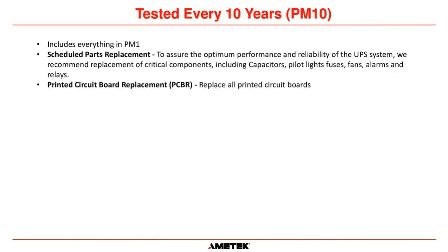And then the last maintenance schedule we have is every 10 years. Okay, a PM10. So that includes everything in the PM1. It also includes replacing the critical components, and that includes the capacitors, the pilot lights, fans, alarms and relays, and all of the circuit boards within the UPS. So it's pretty much you're ripping out the inside of the UPS and you're replacing all of the age-degrading components to make sure you still have a good UPS that's going to work for you for many years to come. Okay, it is much more intrusive, but it does make sure your UPS is back up to as if it was straight out of the factory.